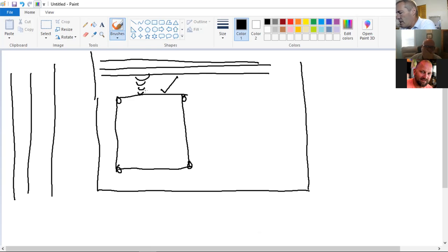It was starting to get the sensation of magnetic induction from that transmission line over there. As soon as that happened, we took a ground rod, put it right down here, and grounded all the lines in the circuit. From that point on, we moved everything further away. So yeah, it has happened at the field.